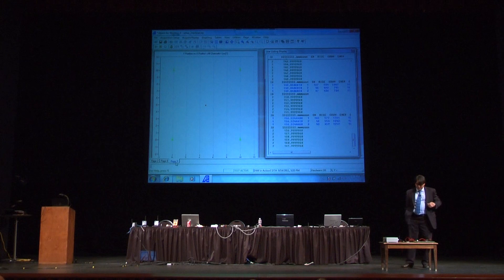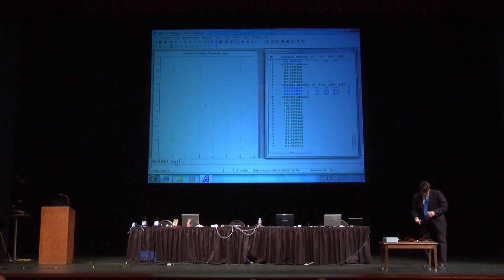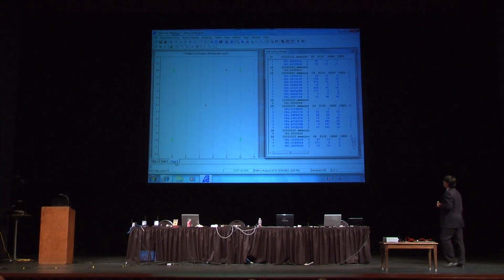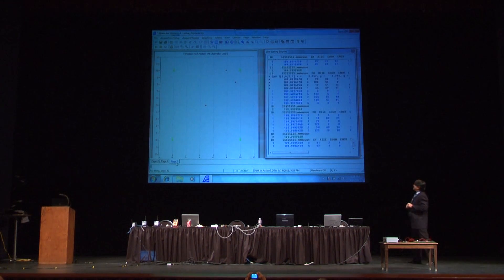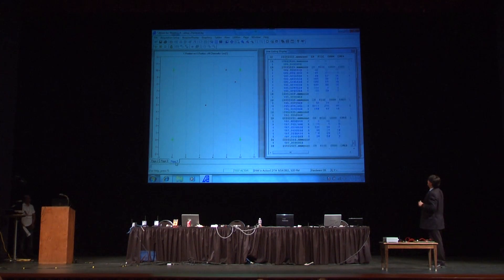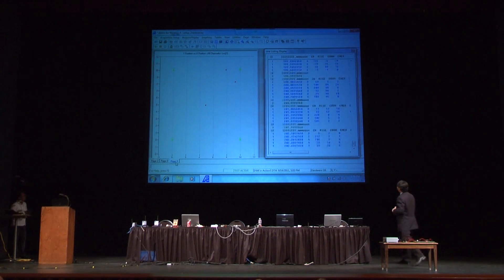Instead of doing the traditional pencil break, I'm going to do a little bit of magic here. I'm going to use a little bit of water, and put in the magic ingredient, which is pop rocks. You can see immediately that you get all kinds of emissions from the pop rocks — some of them are getting located. This is a good way of simulating a source of acoustic emission. Of course, we wish that a source of acoustic emission were that continuous, but they are not.